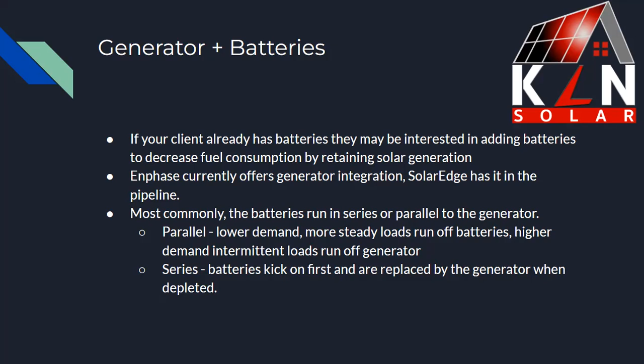The problem though is it requires the same size of battery for backup as you would without a generator. So if your home needed a 40 kilowatt-hour battery anyway, without a generator, it still needs a 40 kilowatt-hour battery. You're not getting savings there, and you're not able to use a smaller battery than you would have otherwise, because the generator here doesn't directly power the loads—it's actually only charging the batteries when needed.